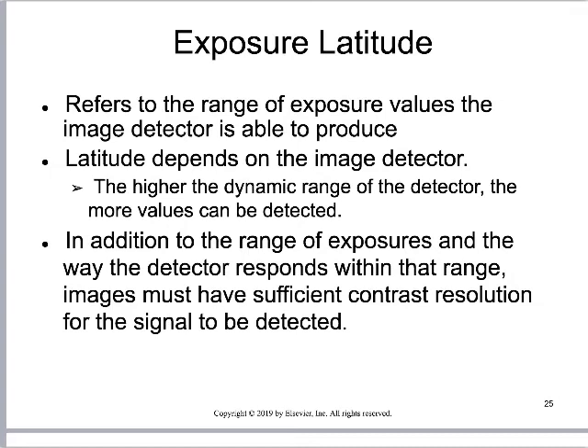The final thing to look at is exposure latitude — how broad an area in which we can make an exposure and still get an image. Latitude depends largely on the image detector. The higher the dynamic range of the detector — the more shades of gray it can represent — the higher the exposure latitude. The exposure latitude of digital imaging systems is much broader than it was in the days of film, so we have a tremendous amount of play in these digital systems.